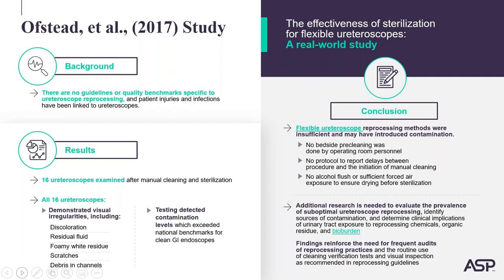All 16 demonstrated visual irregularities, which included discoloration, residual fluid, foamy white residue, scratches, and debris in the channels. All 16 scopes were tested to detect contamination levels, and they exceeded the national benchmarks which have been established for GI endoscopes. The researchers concluded that flexible ureteroscope reprocessing methods were insufficient and may have introduced contamination.